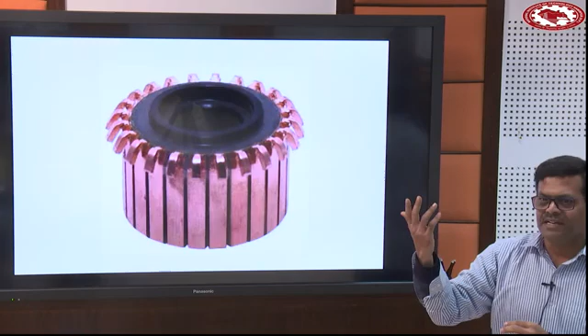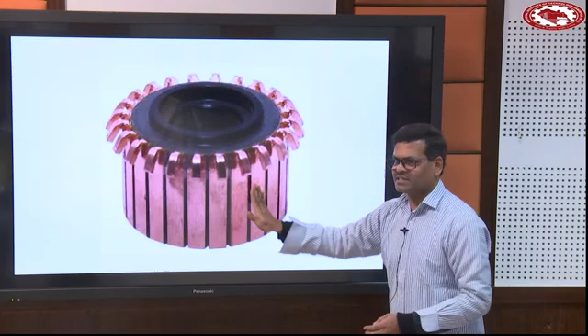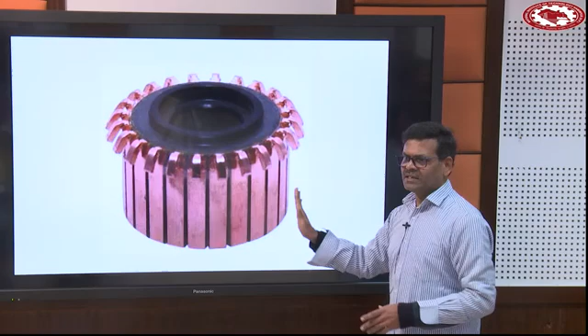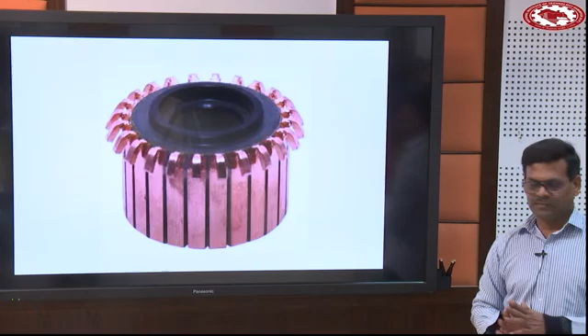With time, there is a possibility of oxide layer formation because of that arc, and this oxide layer will be black in color. Once again, because of that, contact resistance increases. So effectively it's not an efficient system. Periodically it has to be cleaned, or the brushes need to be replaced. So maintenance requirement is more with DC machines. If there is a possibility to get rid of DC machines, that is ideal.